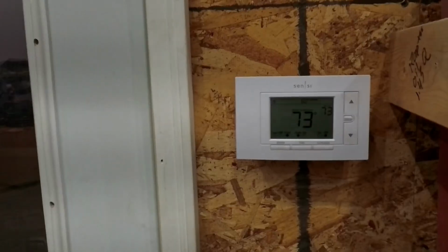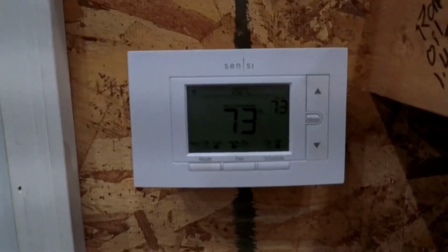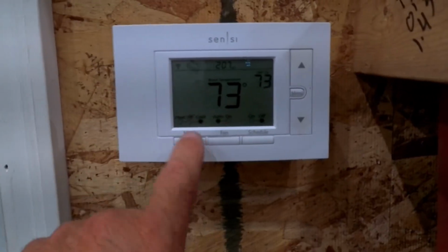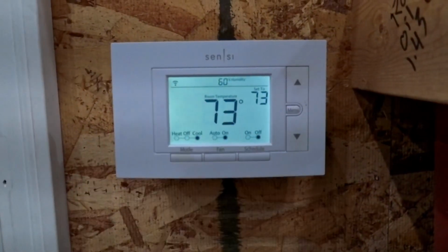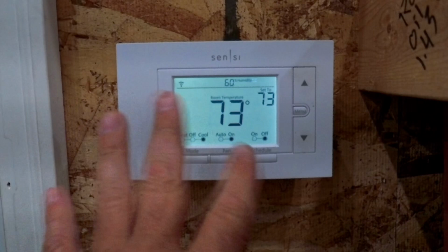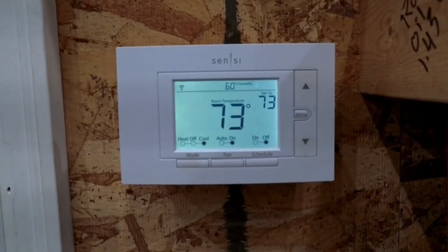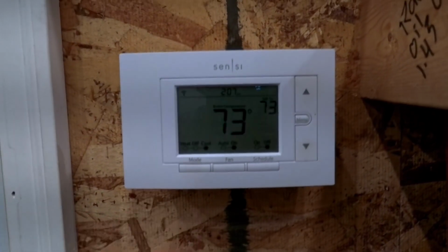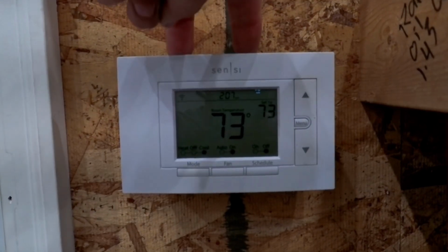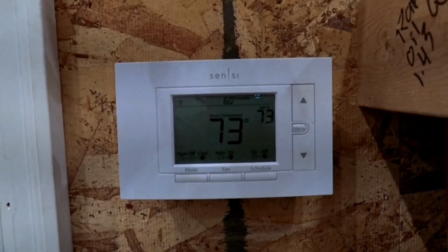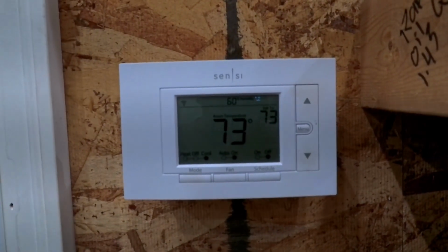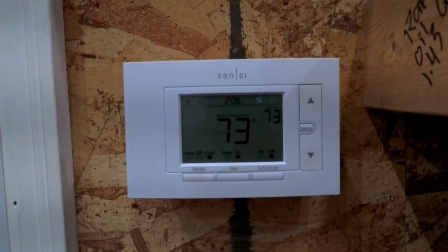What do you do? Well, first things first, we're going to check the thermostat. As we can see, it is lit up, so we know we got power. If you don't have any power or the screen's blank, obviously there's the start of an issue. Now the older units, they have batteries internally, and if those are dead, obviously you're going to have an issue. Take it off, change the batteries, Google it, whatever you got to do.